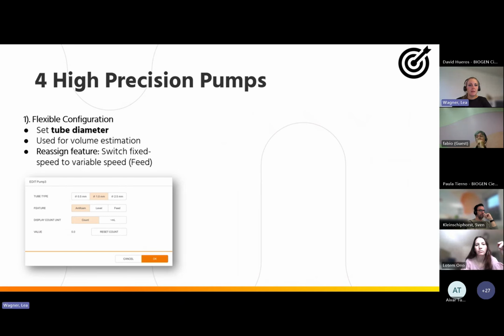Now to the pumps. We have 4 high precision pumps at Minifors 2, which have a flexible configuration. As you can see here on the screenshot, first the customer can choose between 3 different tube types, depending on the flow that is needed. So a small tube diameter for small flows, and for higher flows, the customer can choose bigger tube diameters. And this is what I meant when I said flexible configuration. The feature, or the job of the pump can be changed.